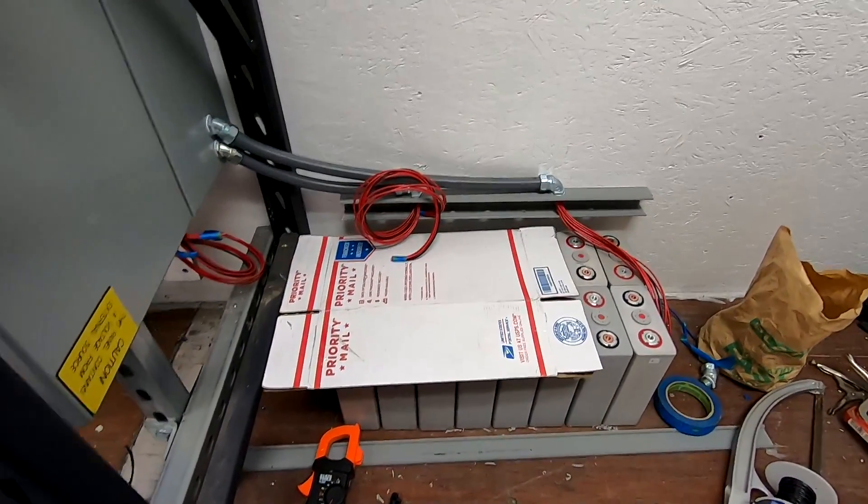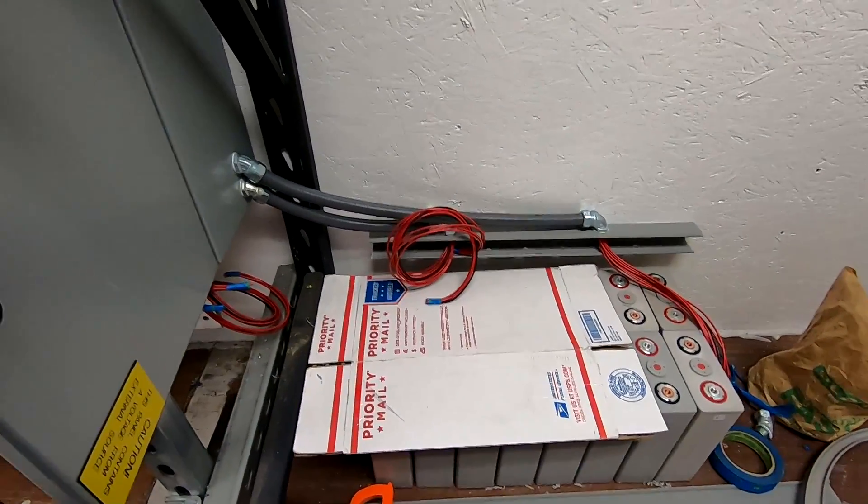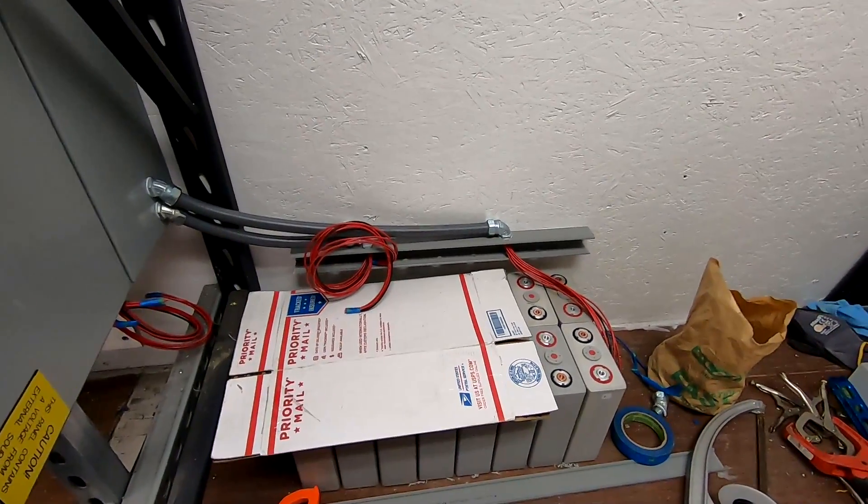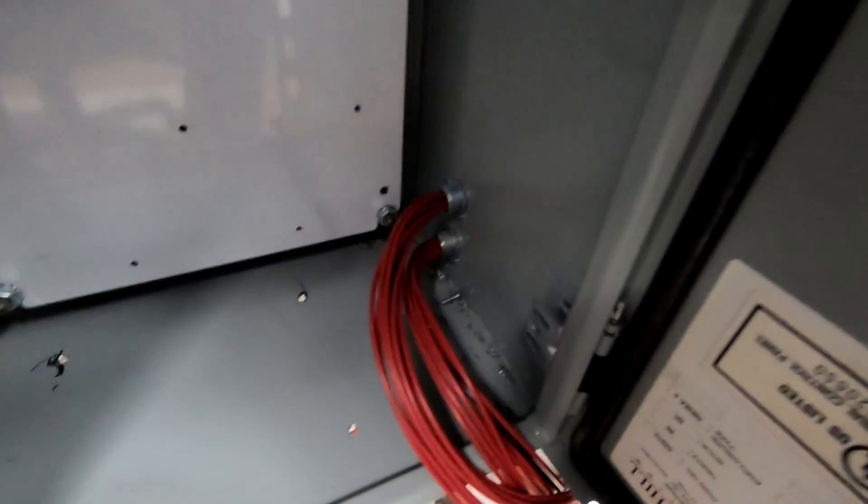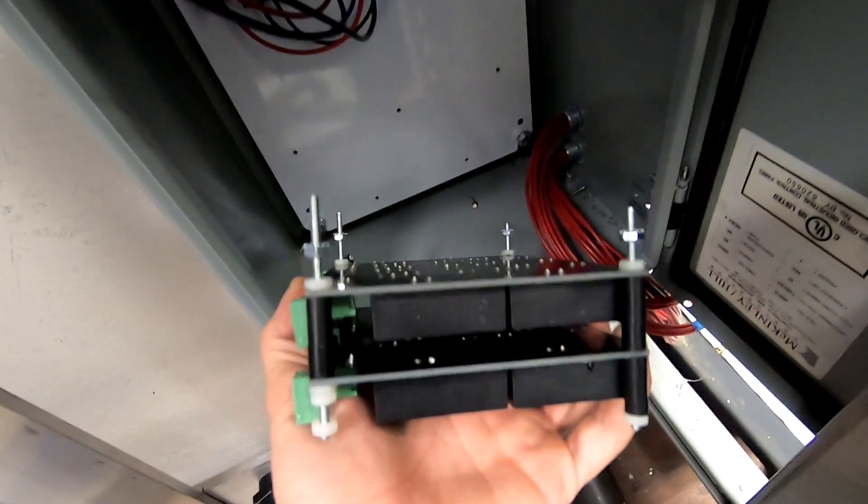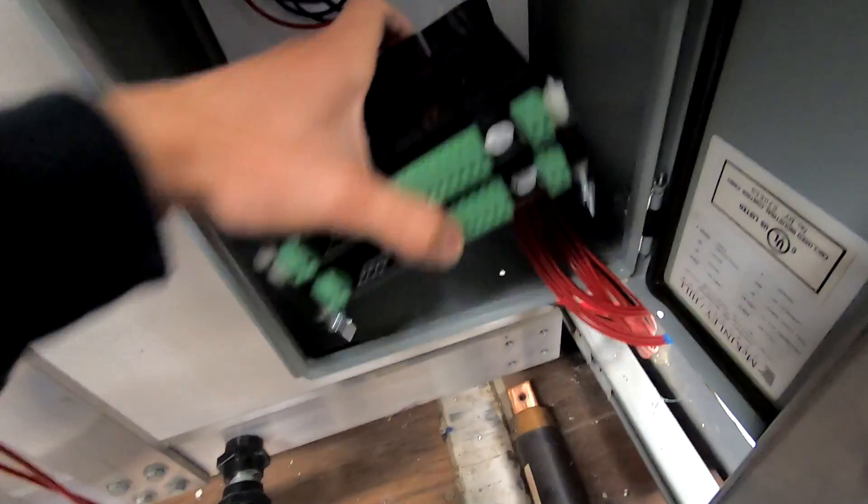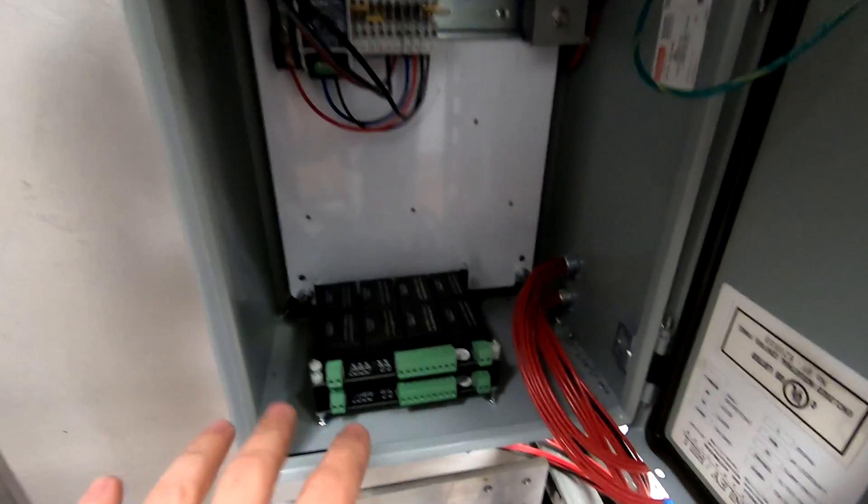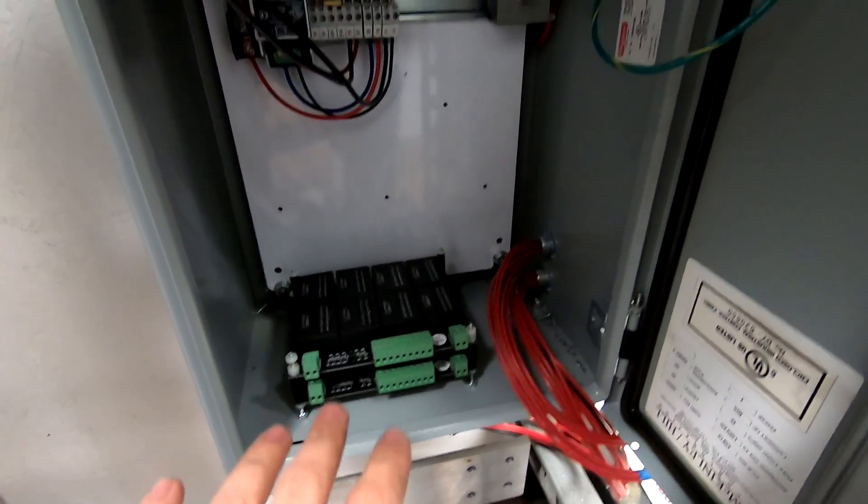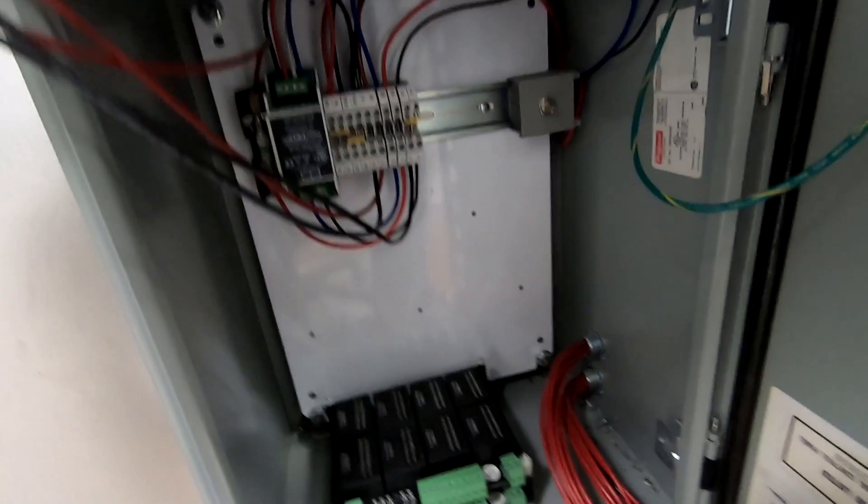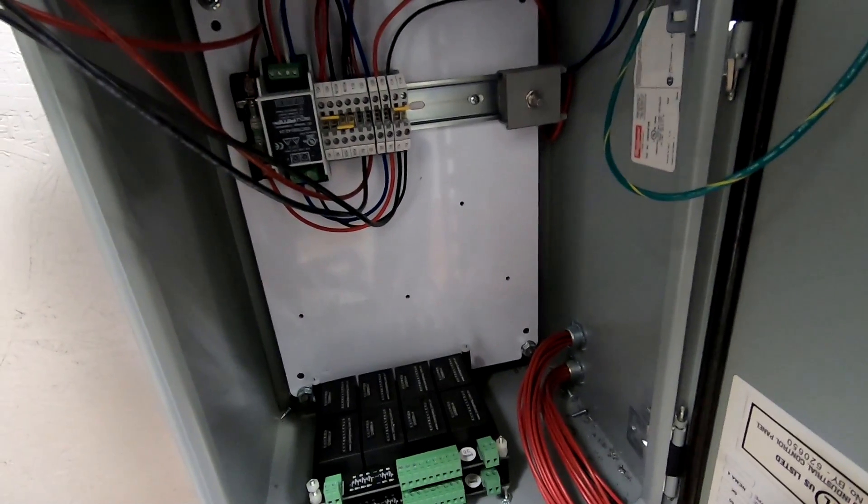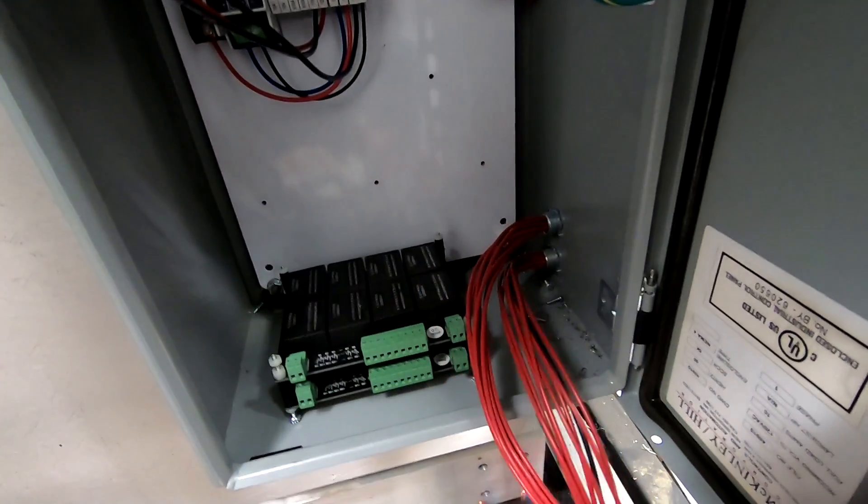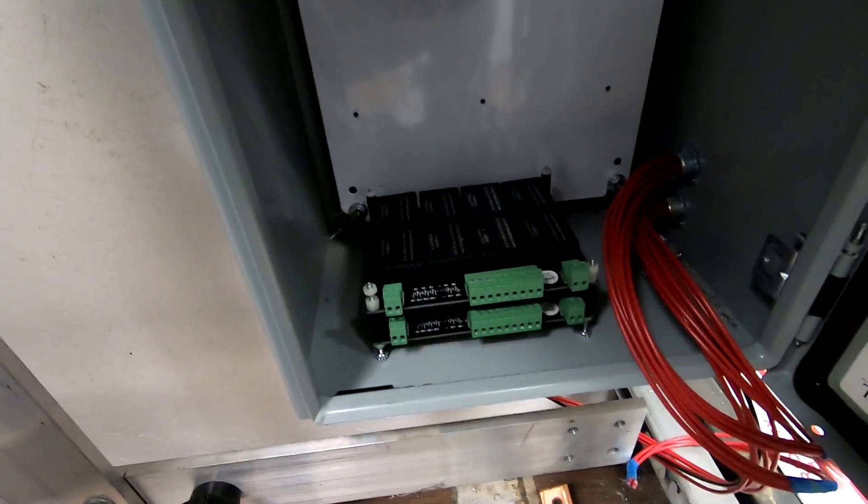So here we are. I've got some cardboard to protect the top of the batteries. I've got a couple of pieces of seal tight half inch ran. All my 14 gauge wire, they're all equal length. I have the wires all in here. I went ahead and drilled four holes for the corners. And I made these stack ups. These are all from Ace Hardware, just nylon spacers. So I'm going to go ahead and stick those in the holes and level that guy out. Go ahead and put the nuts on the bottom. Now I went ahead and put this on the bottom of this cabinet simply for the fact that I wanted to keep this back plane clear. So if I want to add more current sensors or other devices, I have space in this cabinet to do so. So I'm going to go ahead and get these wires all put on the balancers and hooked all up. And then I'll be back.